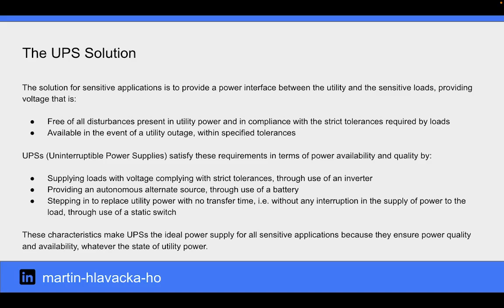UPSs satisfy these requirements in terms of power availability and quality by supplying loads with voltage complying with strict tolerances through the use of an inverter, providing an autonomous alternate source through the use of a battery, and stepping in to replace utility power without any interruption in the supply of power to the load through the use of a static switch. These characteristics make UPSs the ideal power supply for all sensitive applications because they ensure power quality and availability whatever the state of utility power.